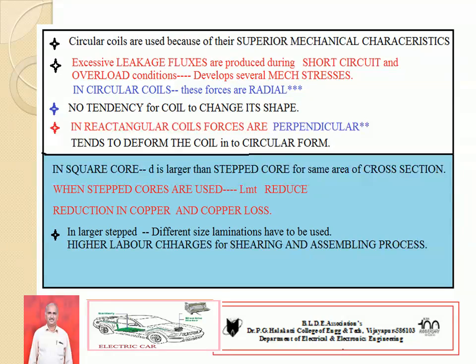The mechanical forces developed on a circular coil act along the radial direction. Hence, there is no tendency of the coil to change its shape, so deformation of the coil does not occur. But on the other side, if rectangular coils are preferred, the mechanical forces developed are perpendicular to the coil. Hence, there is a chance the coil changes shape — rectangular coil becomes circular — so it deforms. Therefore, circular coils are preferred on the stronger side, but rectangular coils are also used depending upon the application, for example in lower-rating shell type transformers.